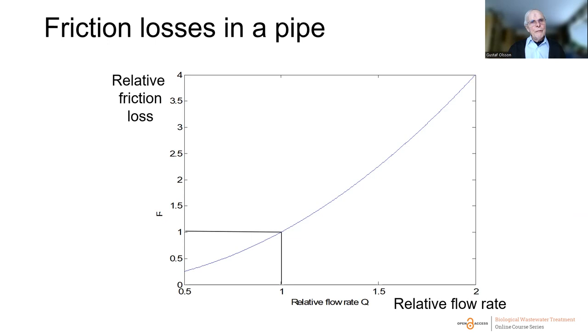There is also friction loss in pipes. If the flow rate doubles, the friction loss increases four times — the friction loss is proportional to the square of the relative flow rate. This means pipe diameter must be designed together with flow rate: a too-narrow pipe results in very high friction loss. This applies to both gases and liquids.